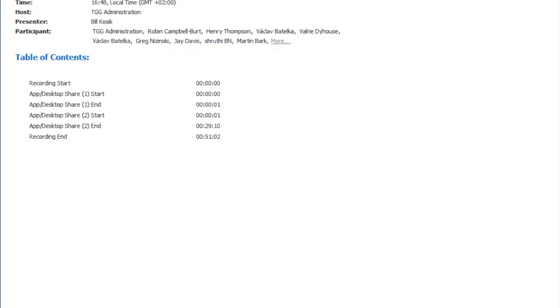So it starts out with the data center, which is more scientifically calculated based on square foot per cabinet, et cetera, and then it goes outward from there and estimates the rest of the building. Now, in other tools we've developed, we can put in the tier level, meaning whether there's a 2N or 2N plus 1, how that system is laid out both on the mechanical and the electrical, and then we can estimate the size of that. That would be a much more refined approach, but for what we're trying to do here, to keep it simple, we're just using multipliers of the data center size. Great question. Okay.